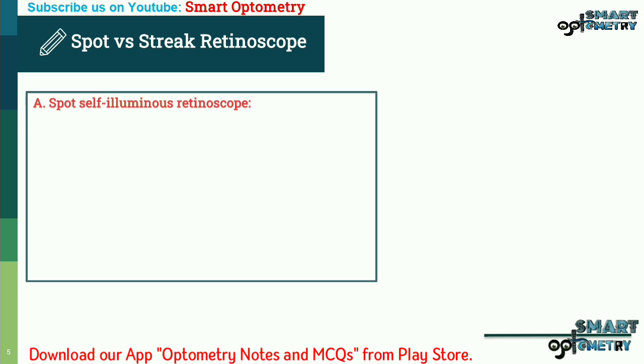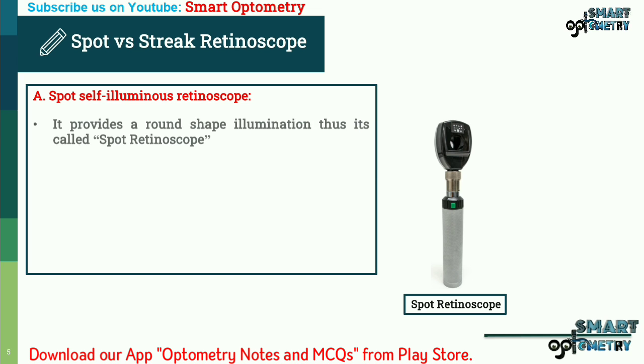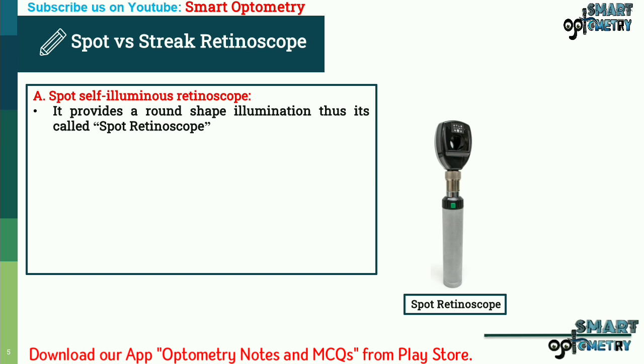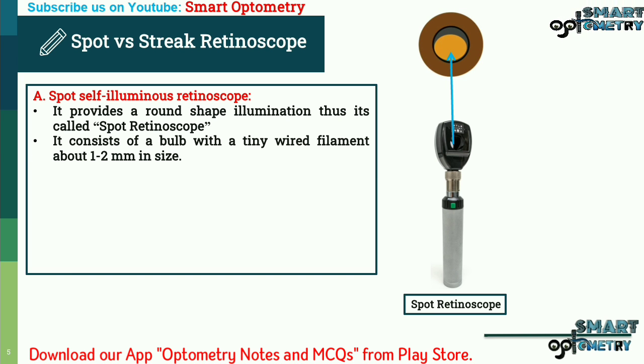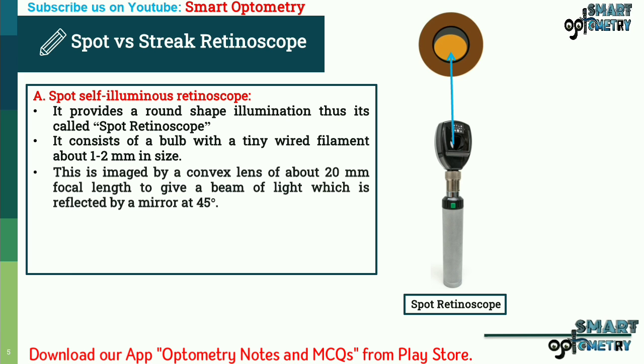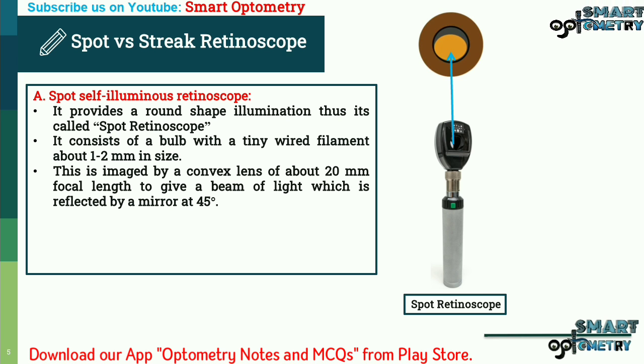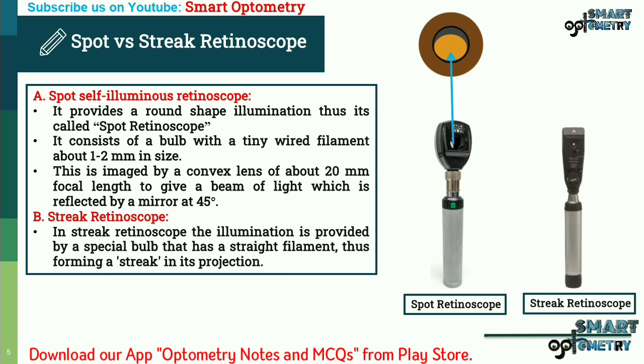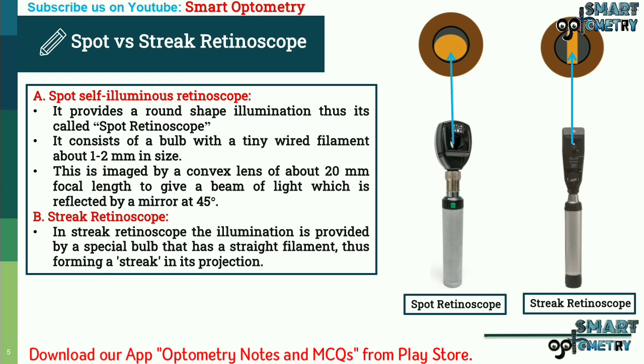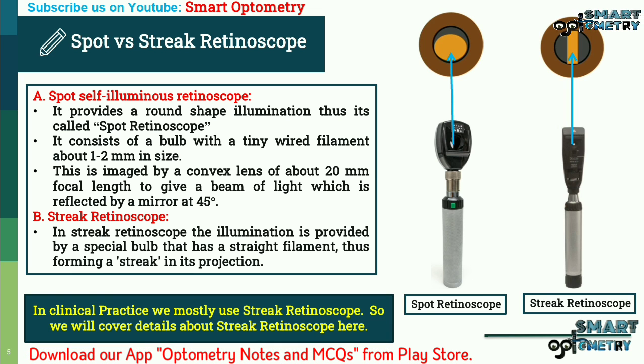Comparing spot versus streak retinoscopes: the spot self-illuminated retinoscope provides a round-shaped illumination and consists of a bulb with a tiny wire filament about 1 to 2 mm in size, imaged by a convex lens of about 20 mm focal length to give a beam of light reflected by a mirror at 45 degrees. In the streak retinoscope, illumination is provided by a special bulb with a straight filament, forming a streak in its projection. In clinical practice, the streak retinoscope is most commonly used.